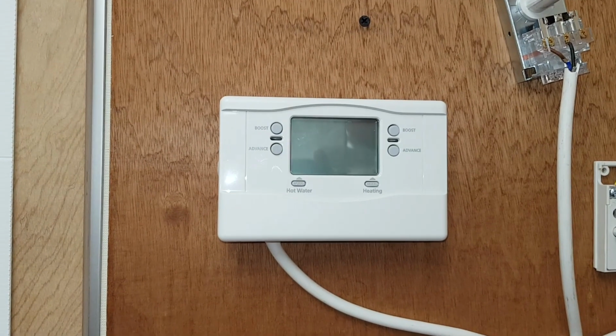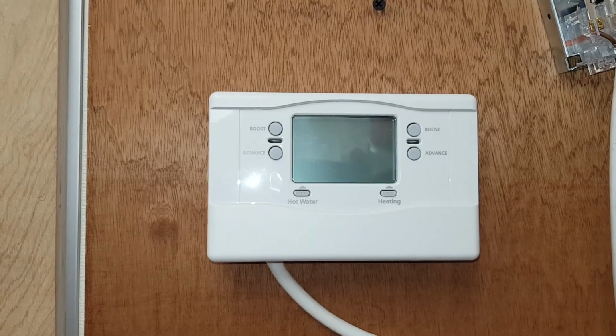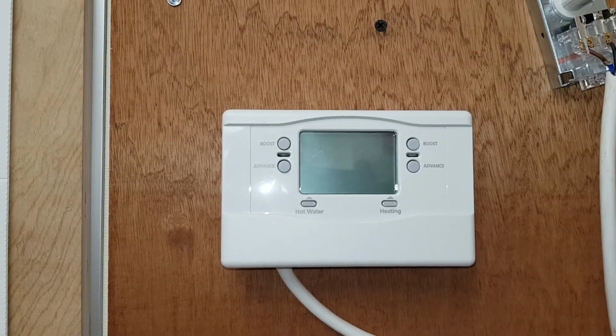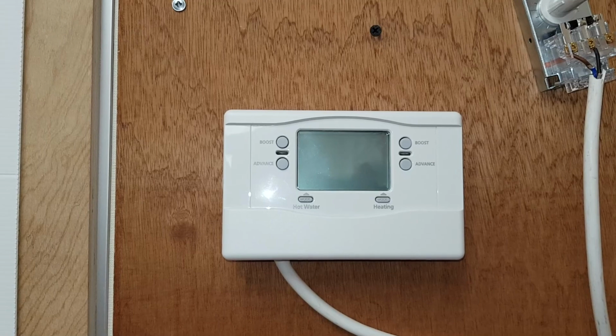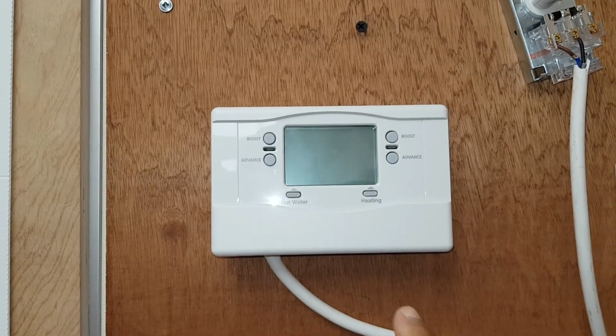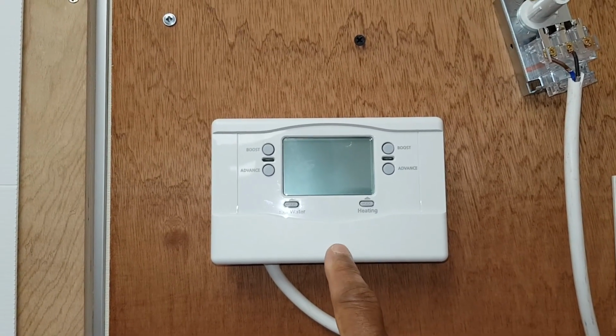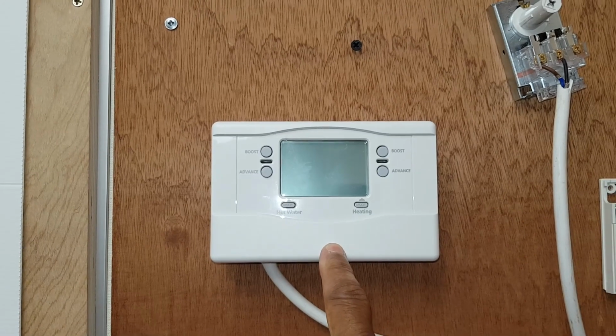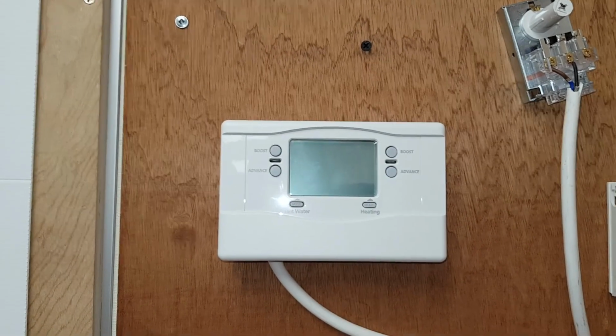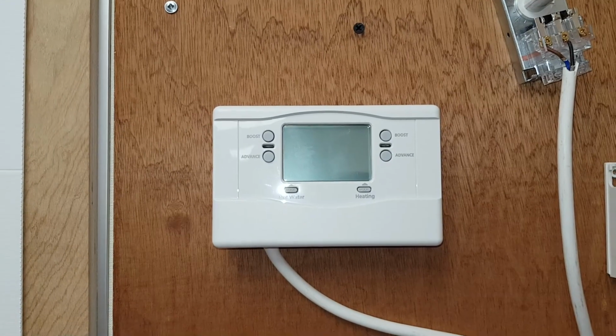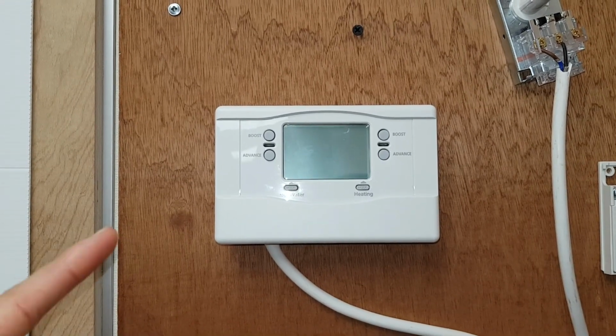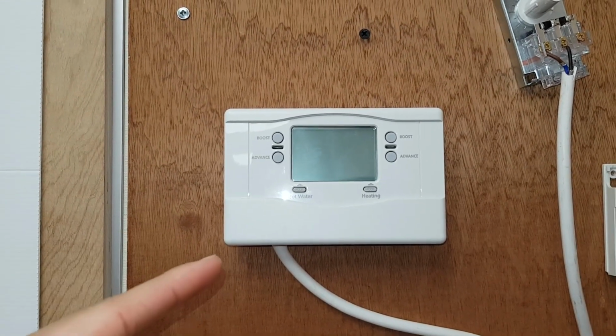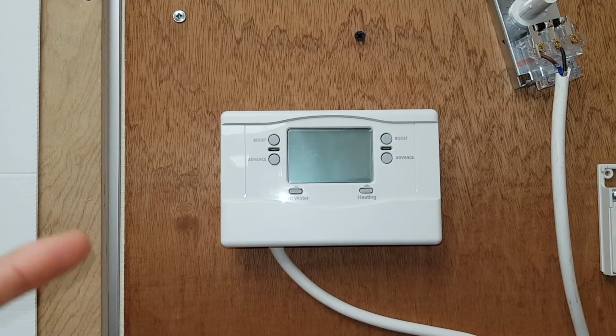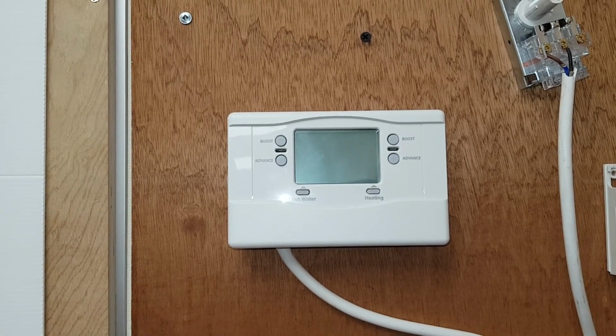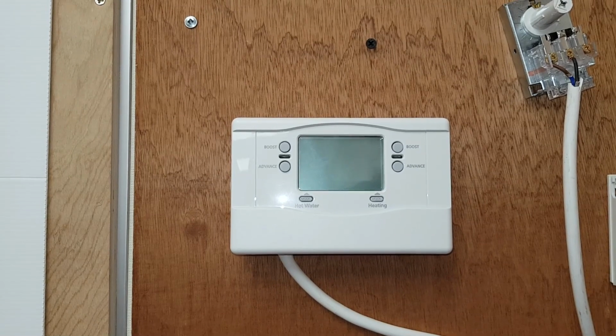Right, Miles, what we're now going to look at is this twin channel programmer. Now what I want you to do is visualize what connections are behind this using our visualization technique, what I've shown you. Remember? So behind there you've got five wires. You've got your live, neutral and earth. And then on terminal 3, you've got your hot water output. And on terminal 4, you've got your central heating output.